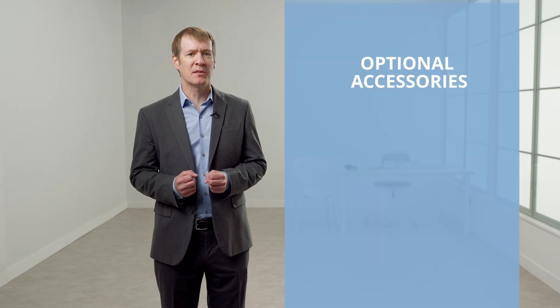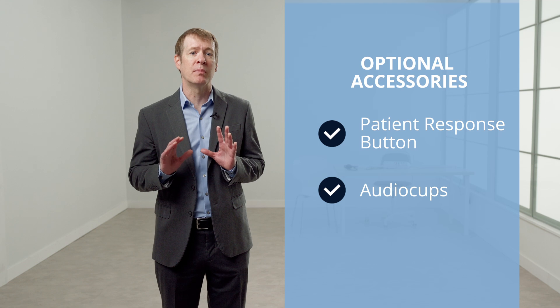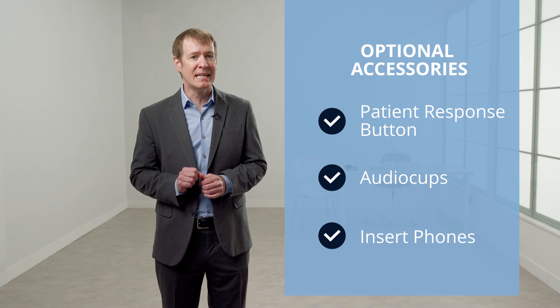Optional items include a patient response button and audio cups, which are circumaural enclosures that fit over the headphones to block out noise. Insert earphones are also available with the GSI 18 and can be added in addition to the headphones. The GSI 18 contains the calibration for both types of transducers for easy transition between styles.